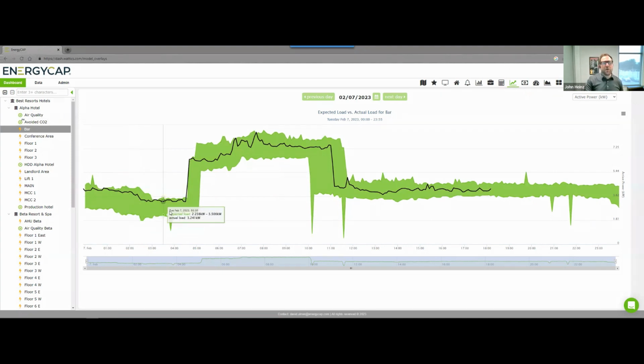This green bar is the expected load. This is the Sentinel—it's saying for this particular meter, it typically turns on around 5 in the morning, peaks out up here, and then starts its shutdown anywhere from 10 to noon, at least starts its setback, and remains about flat for the rest of the evening. So that's the typical profile based on history, day of the week, and certain other algorithms. And then we're trending in black what the actual load is compared to this expected load.